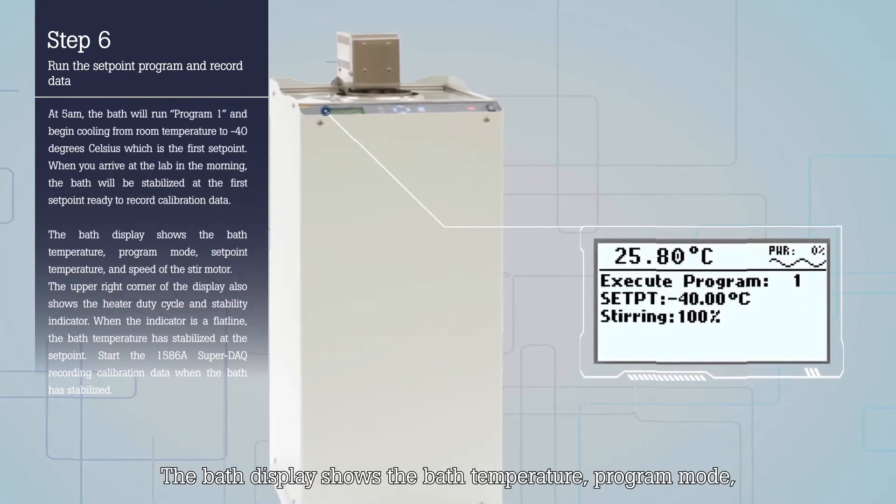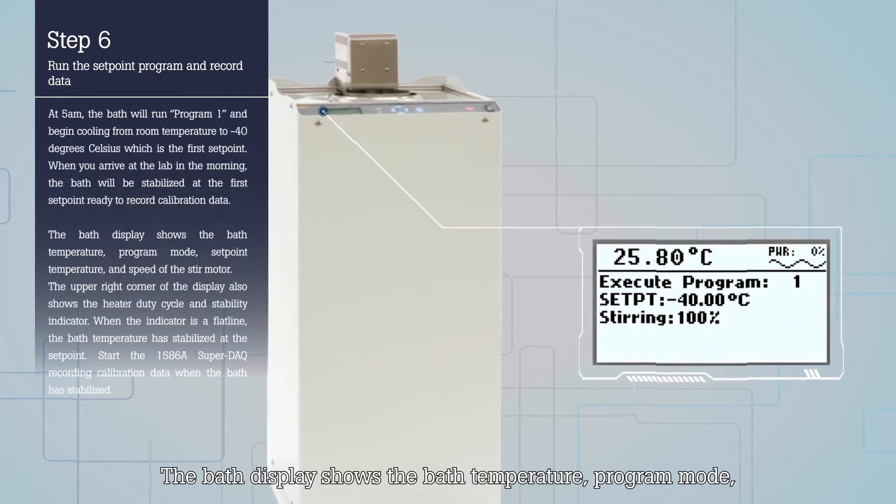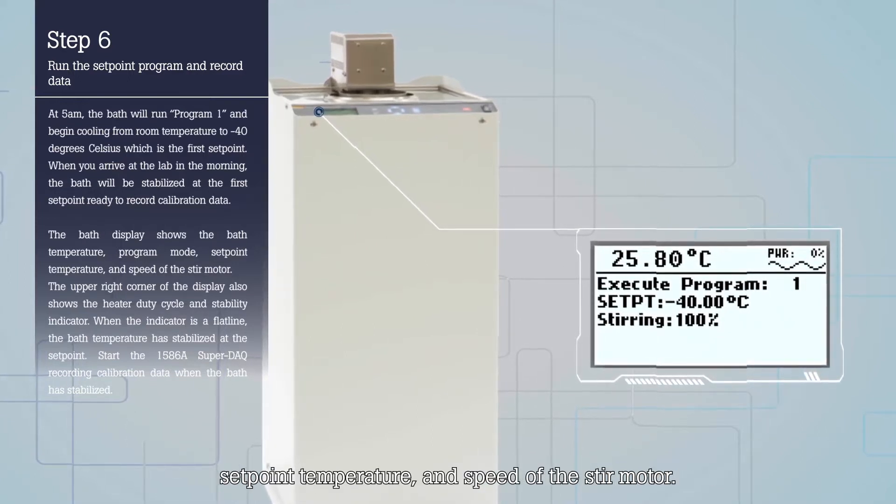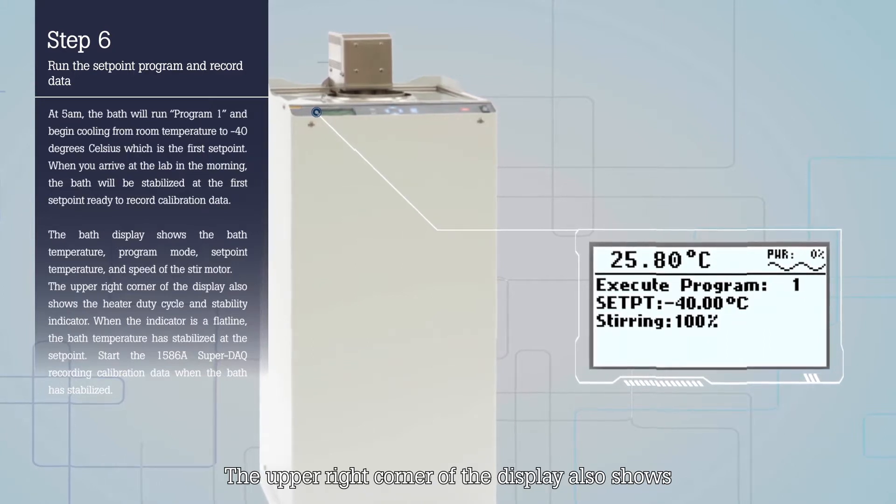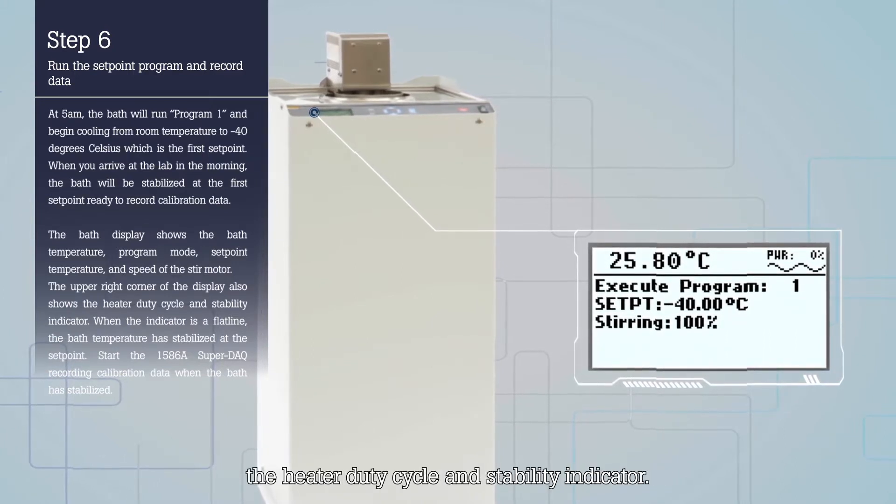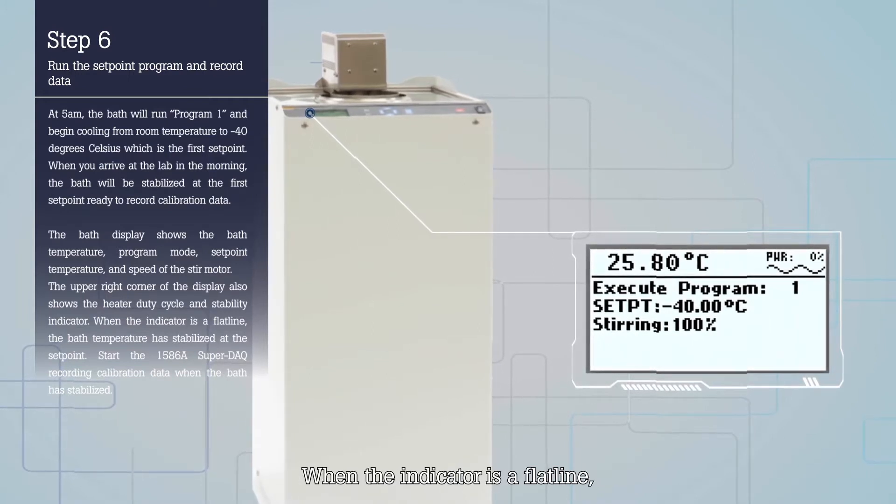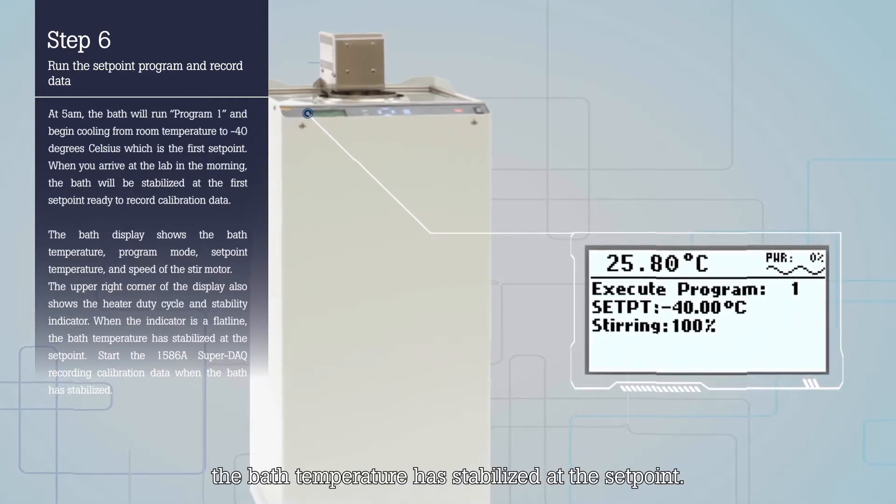The bath display shows the bath temperature, program mode, set point temperature, and speed of the stir motor. The upper right corner of the display also shows the heater duty cycle and stability indicator. When the indicator is a flat line, the bath temperature has stabilized at the set point.